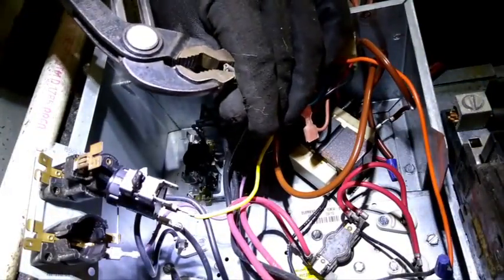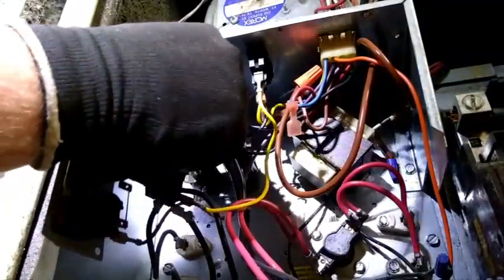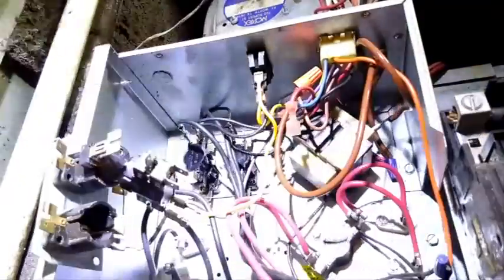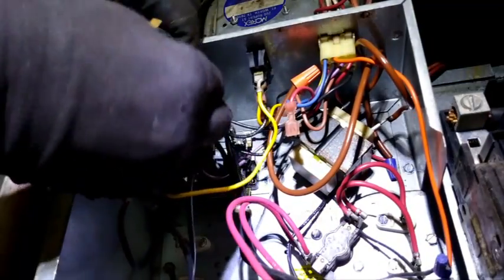As you see, the sequencer fell apart and one of the ceramic push rods fell out of it and the disc fell out of it. So it wasn't in real good shape. They get real brittle over time because imagine there's 20 amps pulling through these little relays all the time. They've got to be pretty beefy because most relays can't handle that amount of amperage.